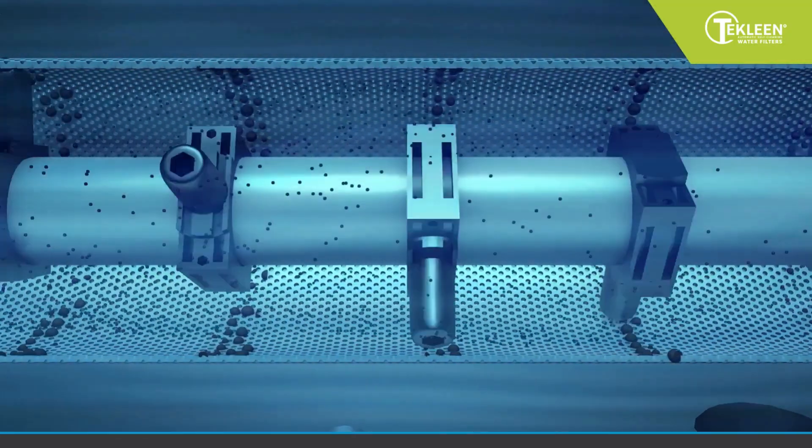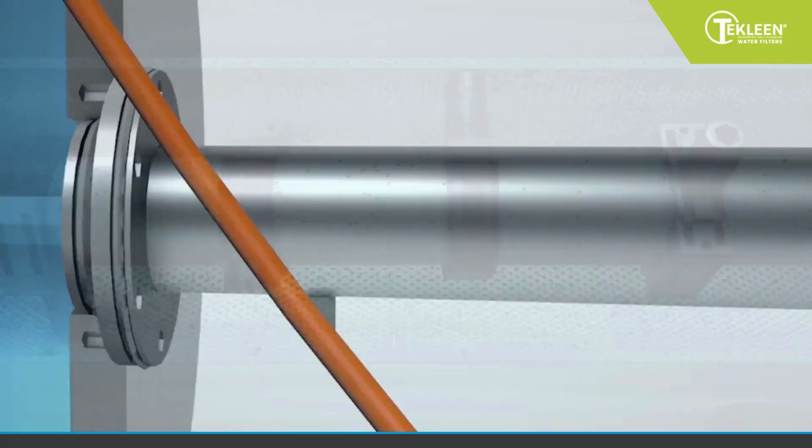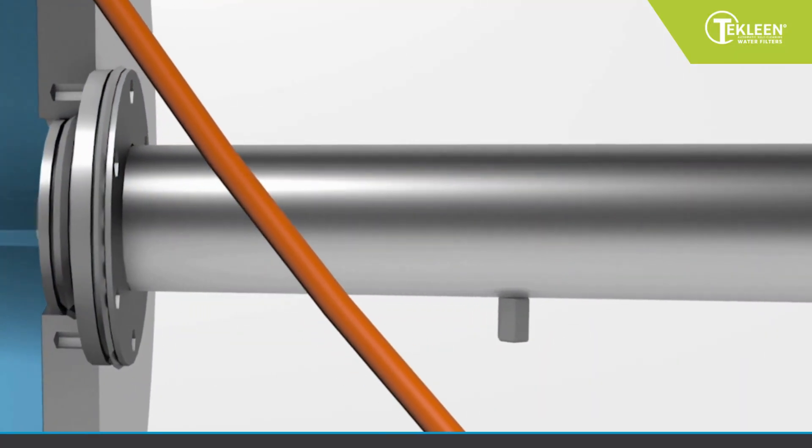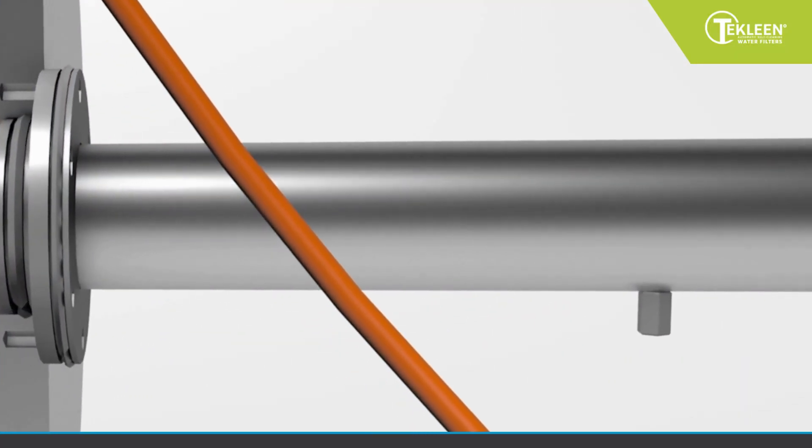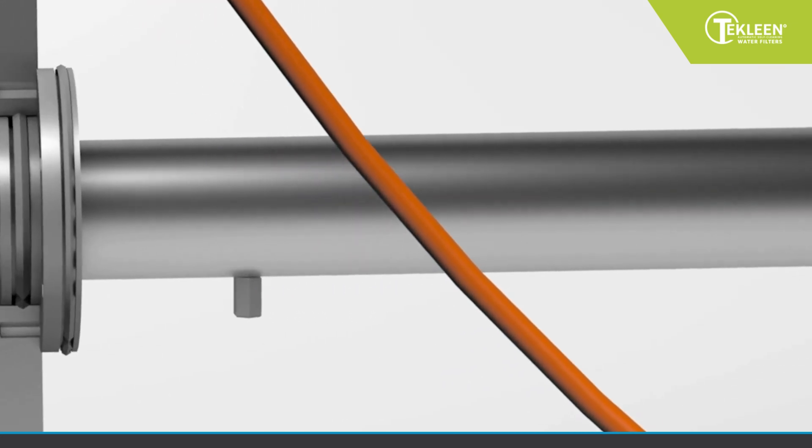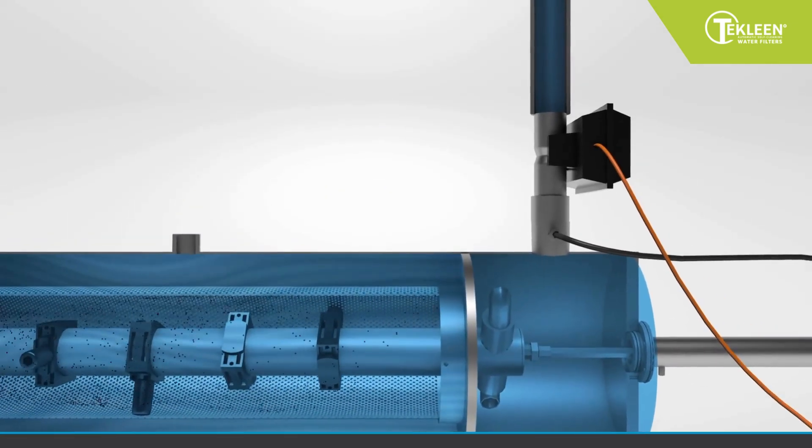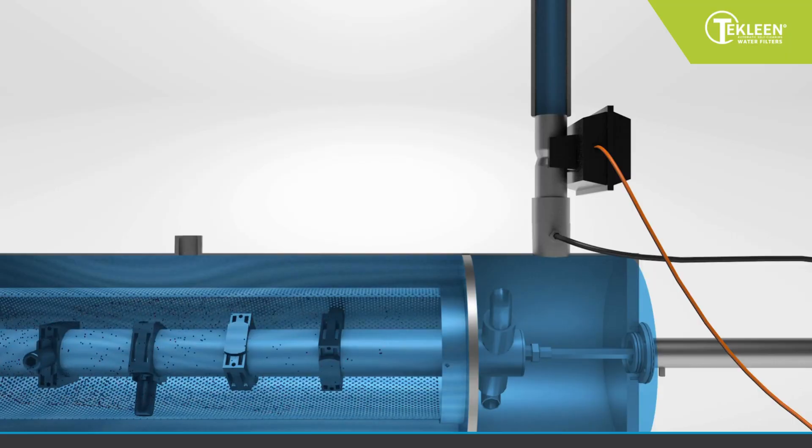The flush time is adjusted to match the travel time of the piston's indicator pin. The pin moves from the home position to fully extended and back home at the conclusion of the backwash cycle. This ensures that the screen is cleaned and ready for use again and again.